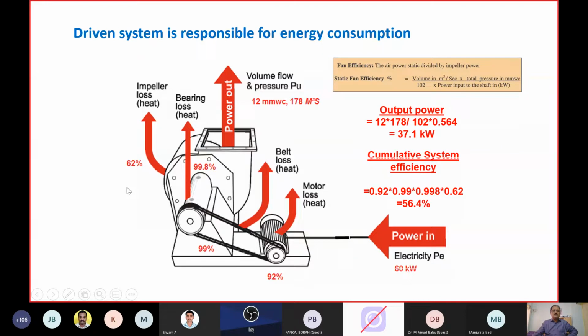So we all know that when you convert energy from one form to another, in this case from electrical to mechanical, the losses will appear in yet another energy form. Here it is heat. So energy cannot be created nor can it be destroyed, as is proved in this class. Therefore, when we look at the total system, the output in terms of flow and pressure gives the cumulative system efficiency, output divided by the input. As you can see here, with all the losses factored in, we arrive at a system efficiency of 56.4%.